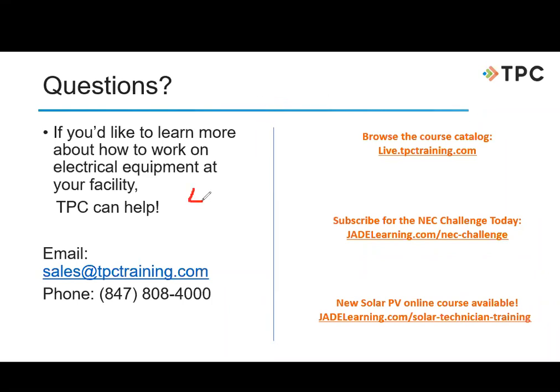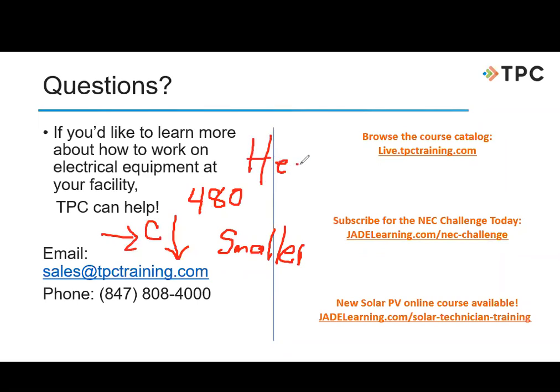Immediately when we go to the higher voltage, we understand that our current is going to be smaller, and with that we're going to have smaller conductors. So we're going to have a little bit of savings by buying a smaller conductor. But what really is going to help us here is that current generates heat, and heat is our enemy in the electrical world. If we can keep our current lower, it's going to produce less heat. When it produces less heat, it is going to allow our equipment to last longer, with less problems.